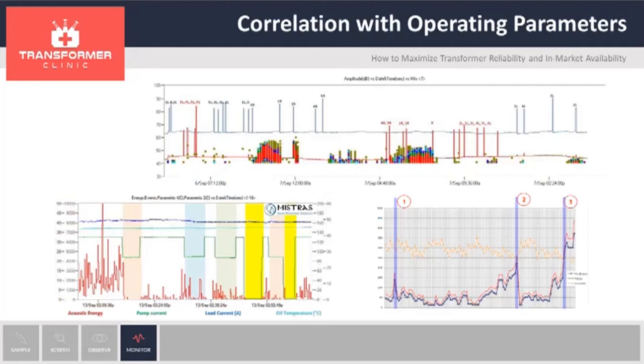This is an example of correlation. Here you can see this is a tap-changer operation in blue, and in red you have the lower positions. At the beginning of this data, there is no activity. Suddenly, when the tap-changer changed to position 1R, the fault was active, and we saw that behavior over time. The recommendation was to not operate the tap-changer on odd positions. This doesn't solve the problem, however it gives the utility some time to plan what is the next step.